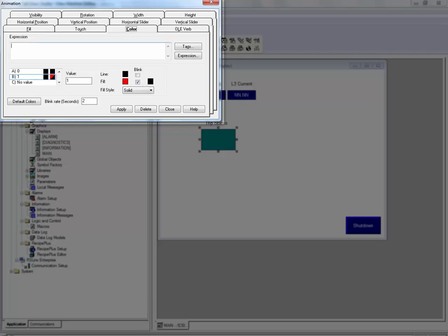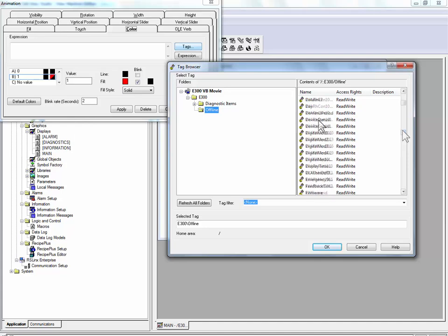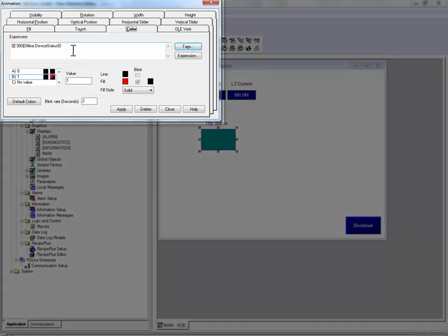Next we will assign this animation to our trip present bit, which is located in the device status 0 parameter. Because other device status bits exist in this parameter, we will use a bitwise AND to only look at the trip present bit, which is located in bit position 0. ANDing device status 0 with the value of 1 specifically looks at the trip present bit.